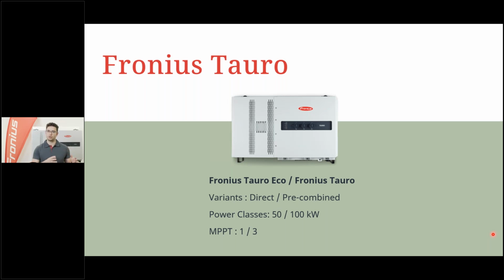So a direct Tauro has pre-configured MC4 connectors at the bottom. So same as with the Verto, you can directly plug in your strings to it. And the pre-combined is more or less for big cable cross sections on the DC side with internally positioned V-clamps. So if you have a string combiner box out in the field, you simply come with a big cable cross section to the Tauro and connect it there on a pre-combined Tauro. So this one, of course, is for big commercial systems and also for off-grid solutions.